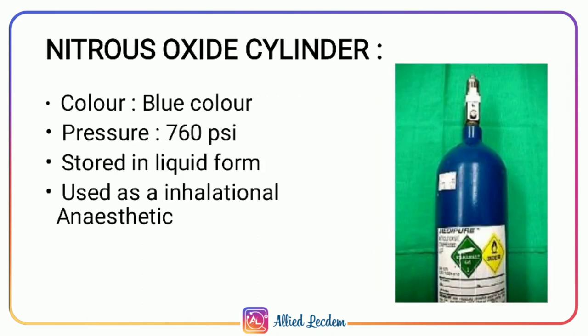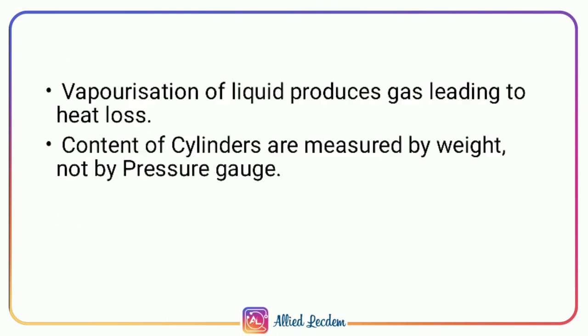The nitrous oxide cylinder is blue in color. The pressure at which nitrous oxide is loaded is 760 psi. It is stored in liquid form and is used as an inhalational agent. Vaporization of liquid nitrous oxide produces gas, leading to heat loss. Because the contents are in liquid form, they are measured by weight and not by the pressure indicated on the gauge.